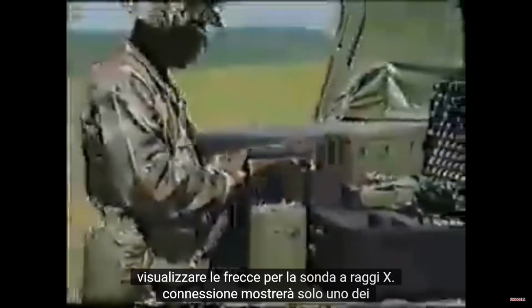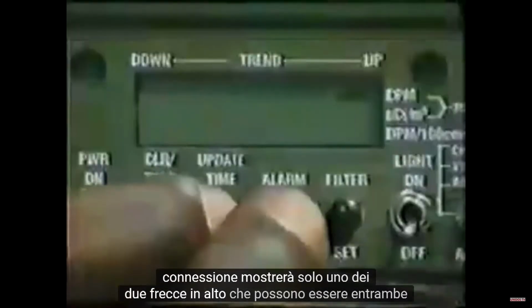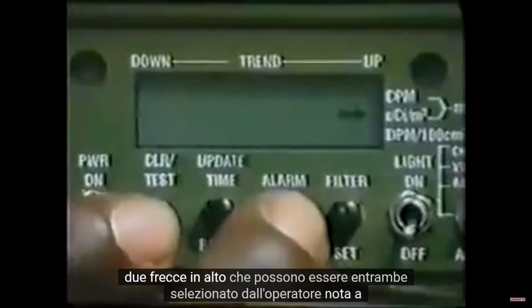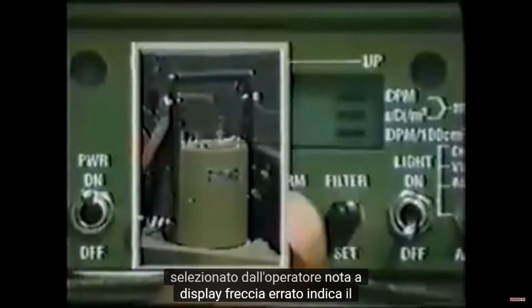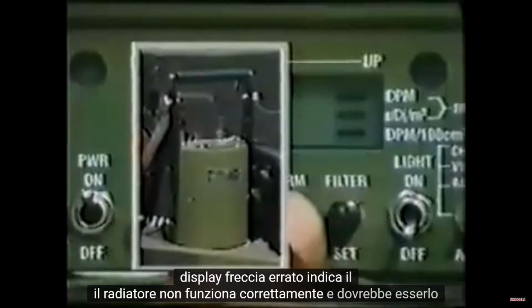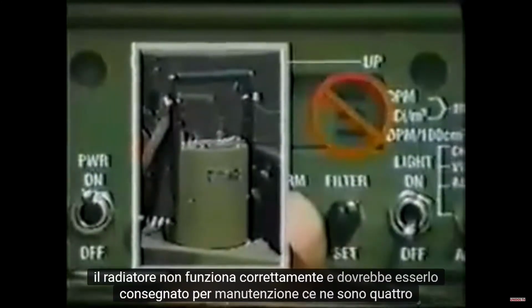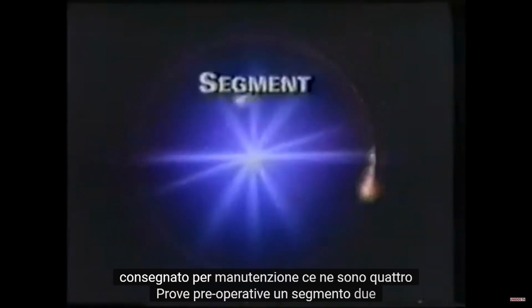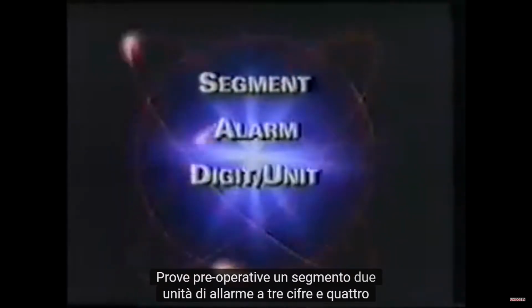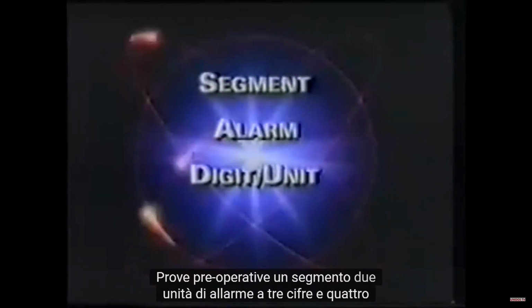For the X-ray probe, the connection will display only one of the 2 top arrows, either of which can be selected by the operator. Note, an incorrect arrow display indicates the Radiac meter is malfunctioning and should be turned in for maintenance. There are 4 pre-operational tests: 1, segment. 2, alarm. 3, digit unit. And 4, electrical, which are done in sequence.